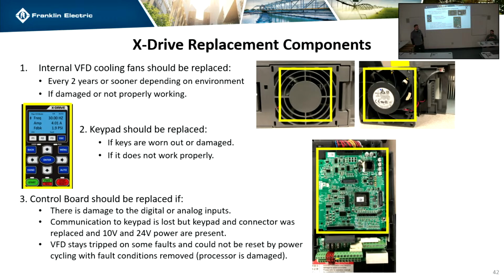I'd say 60 to 70% of people that call in and say their drive is dead, it's not. If a drive's dead, it's obvious: it won't power on, nothing's happening. But if someone's saying that it's stuck doing something or they can't make it do something, the drive's fine, it's programming. Most of the time, tech support will listen to what has happened, what's been changed, and how you want it to work, and then reset the drive. They ignore everything that's happened, reset it back to factory defaults, and run through the programming, and it works.